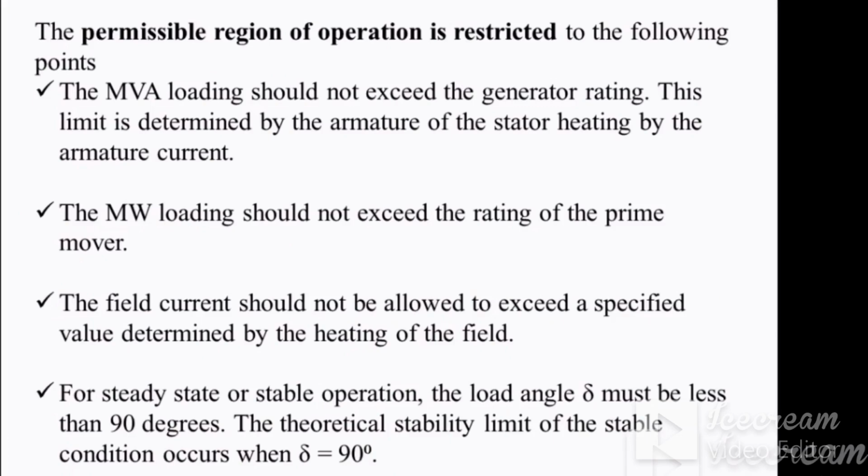The other things which should be taken into consideration: the MVA loading should not exceed the generator rating. Whatever the manufacturer of that particular alternator provided in the nameplate details should be followed very strictly. The MVA loading must not be exceeded, and this limit is determined by the heating of the stator armature by the armature current.